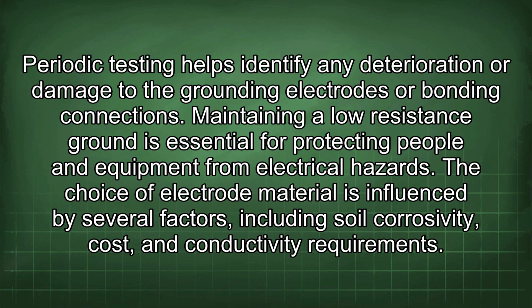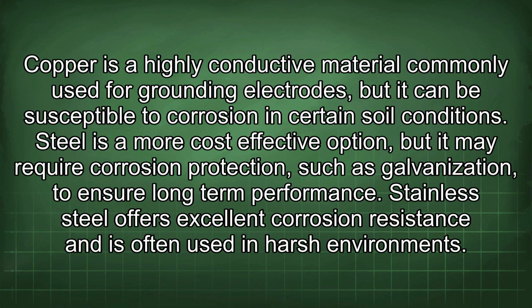The choice of electrode material is influenced by several factors, including soil corrosivity, cost, and conductivity requirements. Copper is a highly conductive material commonly used for grounding electrodes, but it can be susceptible to corrosion in certain soil conditions. Steel is a more cost-effective option, but it may require corrosion protection, such as galvanization, to ensure long-term performance. Stainless steel offers excellent corrosion resistance and is often used in harsh environments.